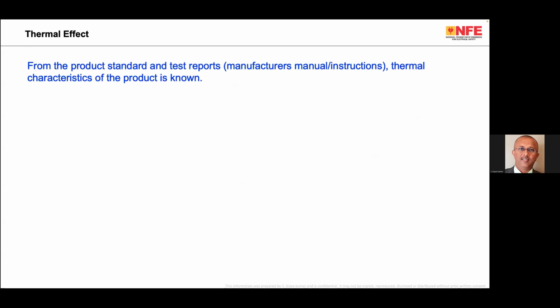Basically, from the product standard and its test reports, the thermal characteristics of the product are known. Finally, the product manufacturer tells you the amount of heat produced from the equipment under normal condition. Of course, going through all these complicated testing of the components is not the job of a user. It is the job of the manufacturer of the electrical equipment.